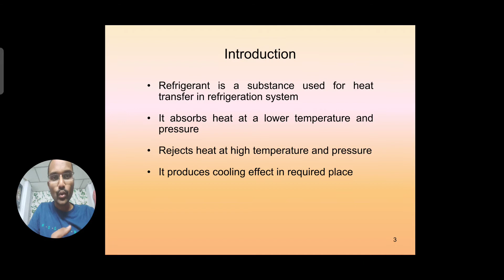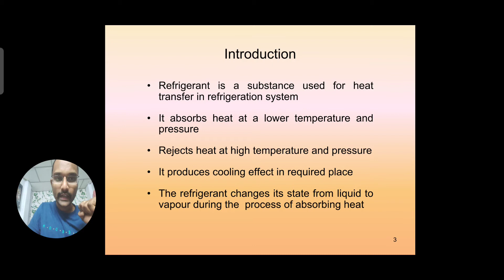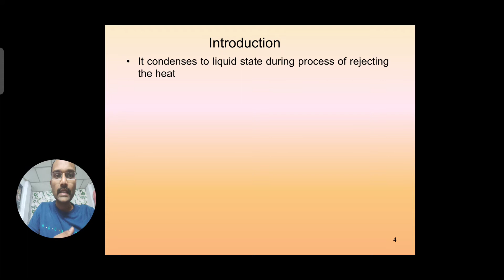As earlier discussed, the refrigerant changes its state from liquid to vapor form, as we have seen in the VCR system. The refrigerant, the heat carrying medium, changes its state from liquid to vapor form. It is a vaporization process which happens in the evaporator. During this process it absorbs heat from the source, at the low temperature region, in the evaporator. So this process is the evaporation process. In a similar way the condensation also happens. It means the phase changes from the vapor form of refrigerant to the liquid form, where it condenses by rejecting the heat to the surroundings. This happens in the condenser, as we have seen in the VCR system.